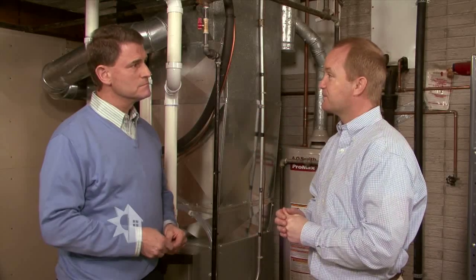Oh yes, very essential. The ductwork is very important. Most people, when they think of their heating and cooling system, identify just the equipment. But really, it's a complete system. It includes the equipment, the ducts, the thermostats, grills, registers, and so on. What's really important to a homeowner is their comfort and air quality in the room, so this has to get to the room somehow, and that's what makes the duct system so very important.